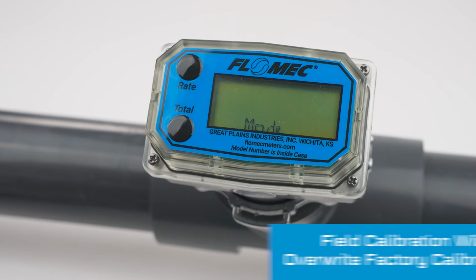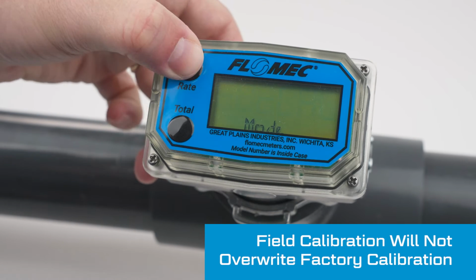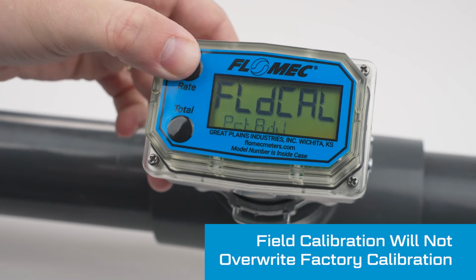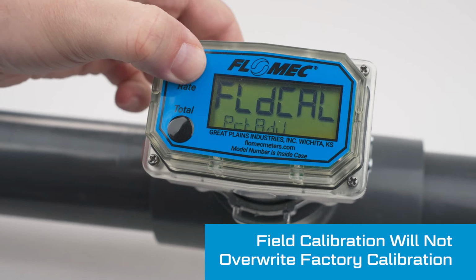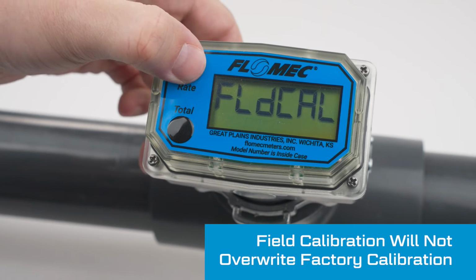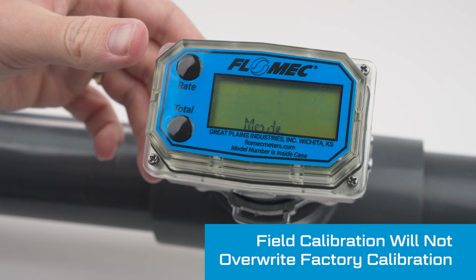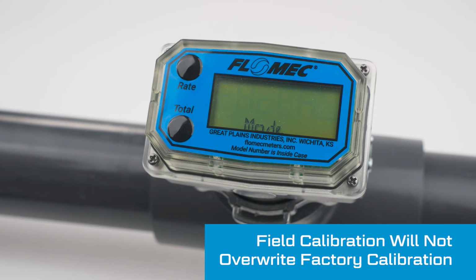Next, the meter will prompt you to select a field calibration method. Press the Rate button to select between Factory Calibration, K-Factor Entry, Percentage Adjust, and Dispense Display. Use the Rate button to select your desired field calibration method and press the Total button to confirm your selection. If no field calibration is desired, select Factory Calibration.